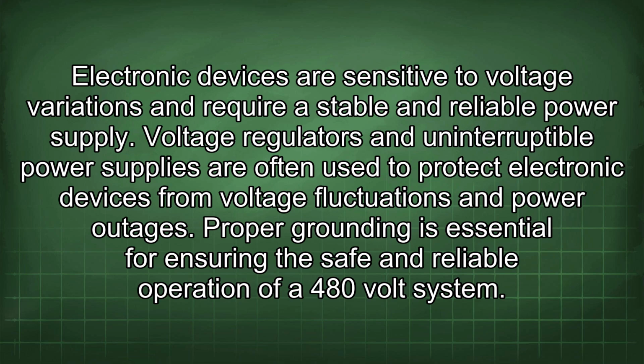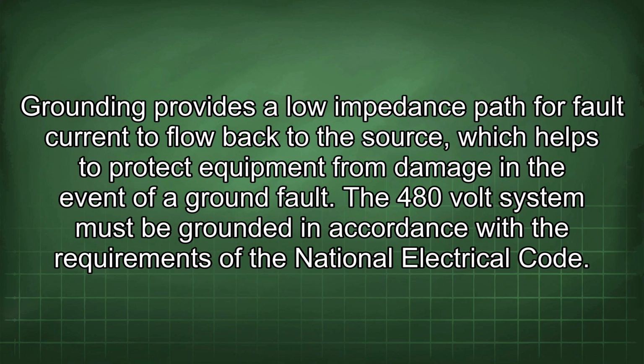Proper grounding is essential for ensuring the safe and reliable operation of a 480-volt system. Grounding provides a low impedance path for fault current to flow back to the source, which helps to protect equipment from damage in the event of a ground fault. The 480-volt system must be grounded in accordance with the requirements of the National Electrical Code.